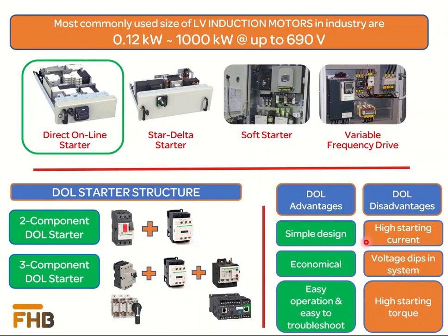Due to the high starting current, the DOL starter also produces a voltage dip in the electrical system and affects other consumers connected to the same line. The DOL starter also produces high starting torque as compared to other starting techniques, and the load therefore must be suitable to bear this large value. Due to these reasons, the DOL starter is mostly used for small motors.